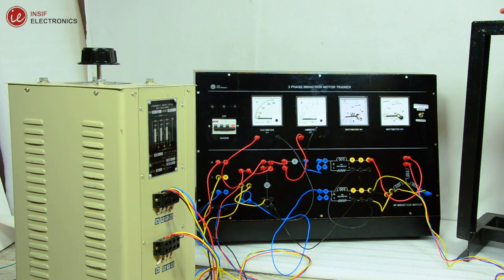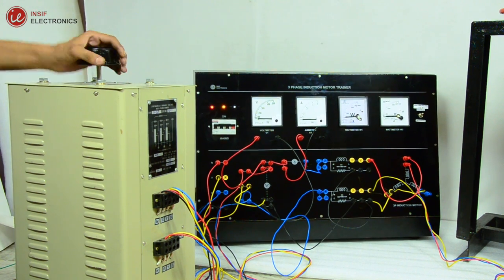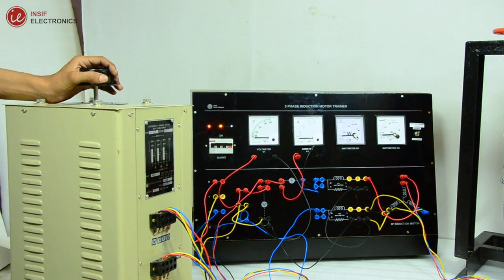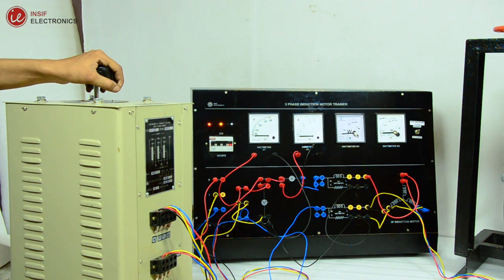Now switch on the panel by pulling up the MCB. This is block rotor test so be careful while increasing the voltage as the current should not exceed the rated current. Increase the voltage carefully and stop increasing as soon as the current reaches to the rated current that is 2A.